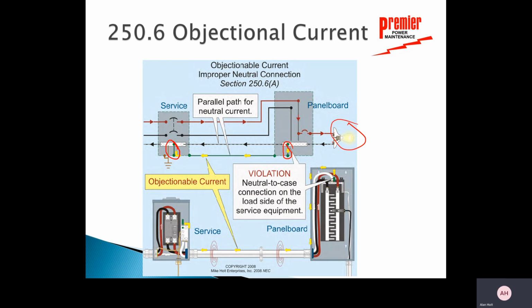So this ground current has a choice. The simple load current can go back on the neutral, or it can go back on the ground. This is not supposed to be a current carrying conductor. The neutral itself is a current carrying conductor. And I can see that neutral case connection on the load side of service equipment. I see that little connection right there where the neutral is connected to ground. That needs to be removed on this panel board because I've already got it connected at the service entrance.